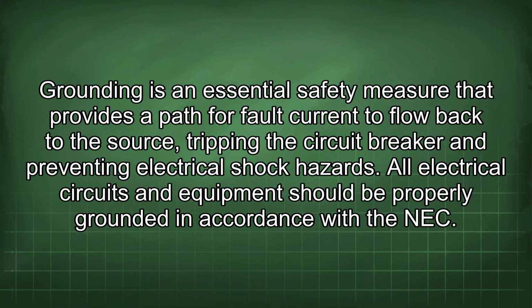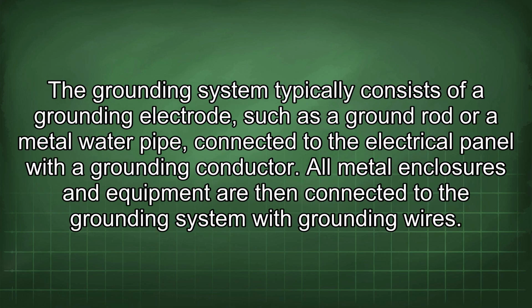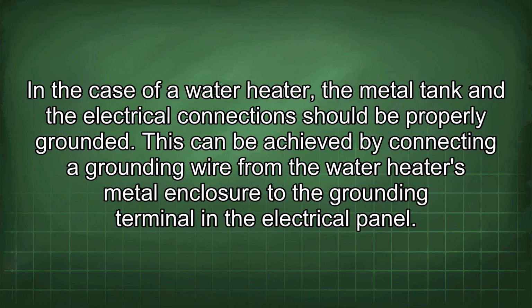All electrical circuits and equipment should be properly grounded in accordance with the NEC. The grounding system typically consists of a grounding electrode, such as a ground rod or a metal water pipe, connected to the electrical panel with a grounding conductor. All metal enclosures and equipment are then connected to the grounding system with grounding wires. In the case of a water heater, the metal tank and the electrical connections should be properly grounded.